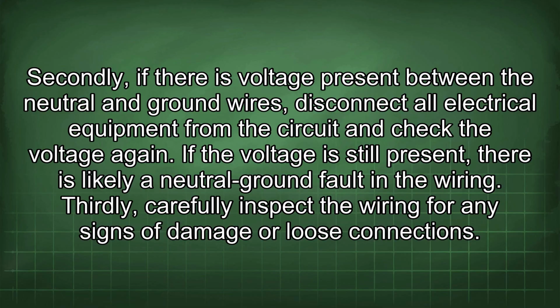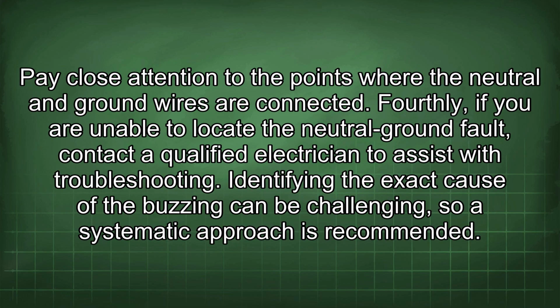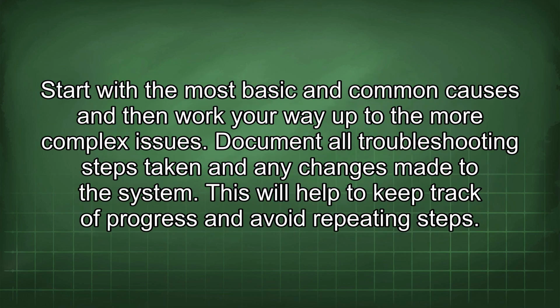Thirdly, carefully inspect the wiring for any signs of damage or loose connections. Pay close attention to the points where the neutral and ground wires are connected. Fourthly, if you are unable to locate the neutral ground fault, contact a qualified electrician to assist with troubleshooting. Identifying the exact cause of the buzzing can be challenging, so a systematic approach is recommended. Start with the most basic and common causes and then work your way up to the more complex issues. Document all troubleshooting steps taken and any changes made to the system. This will help to keep track of progress and avoid repeating steps.